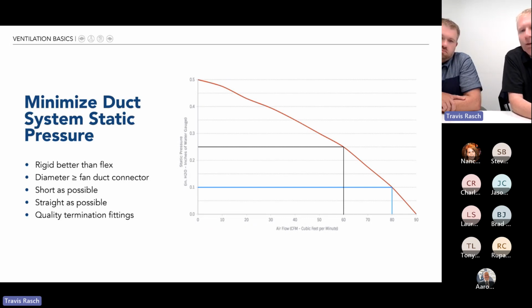So as you can see, as static pressure is lower, it's going to perform better. If you follow that blue horizontal line across, that's at 0.1 inches, you'll see this fan moves 80 CFM. So that's the standard rating point that HVI established decades ago. So when you see a rating point for most ventilation products, it's going to be at a 1/10 inch. So if you're buying an 80 CFM fan, it's going to be at a 1/10 inch.